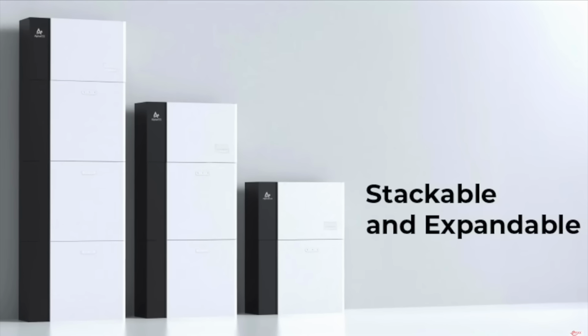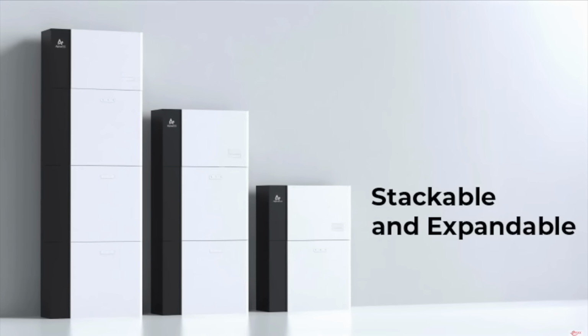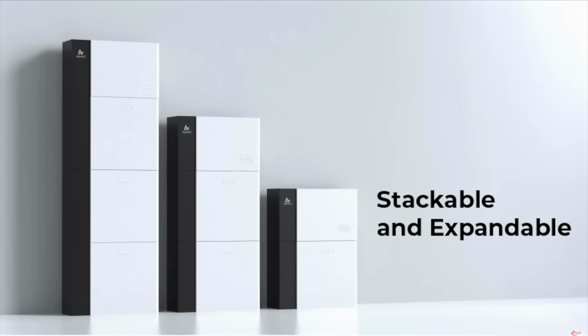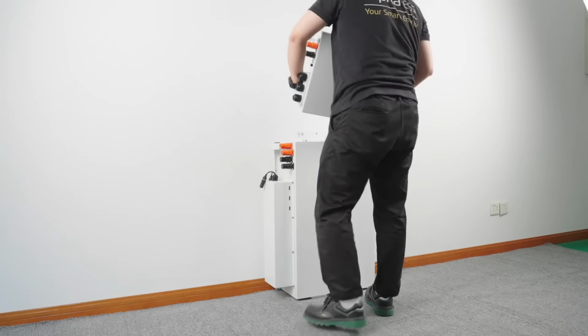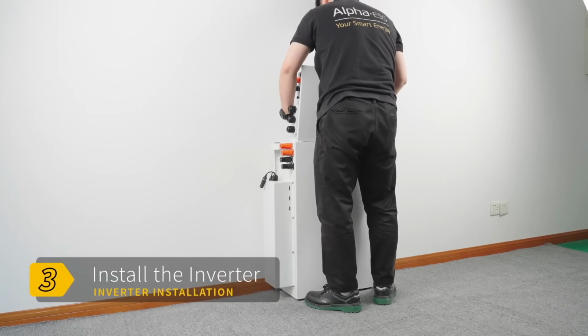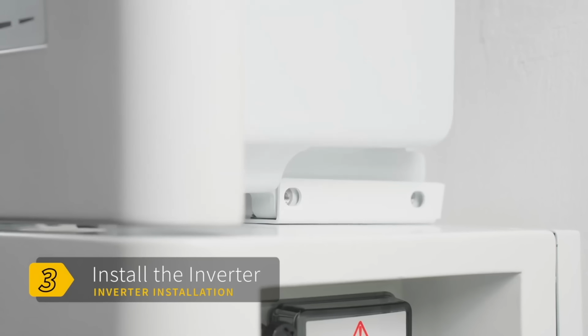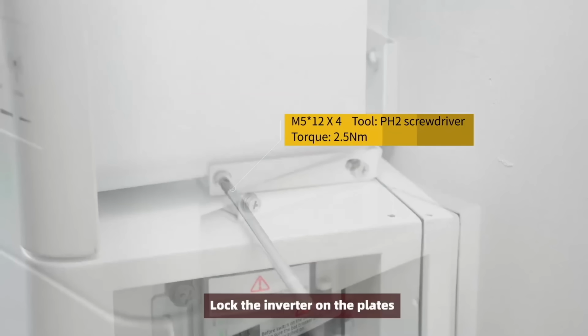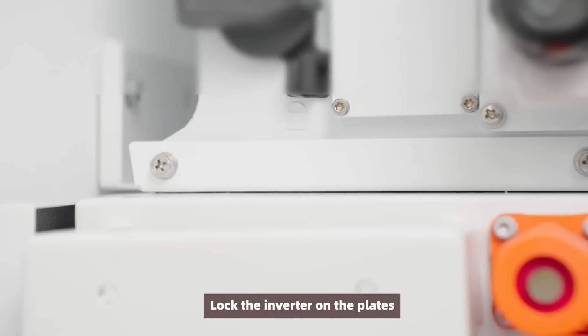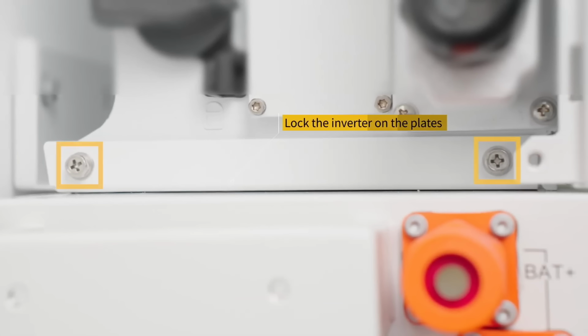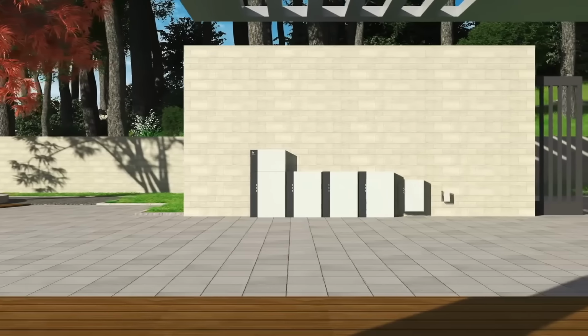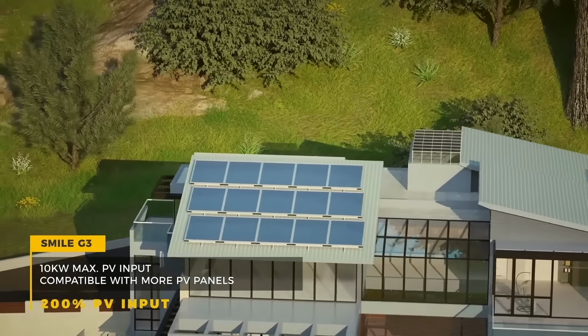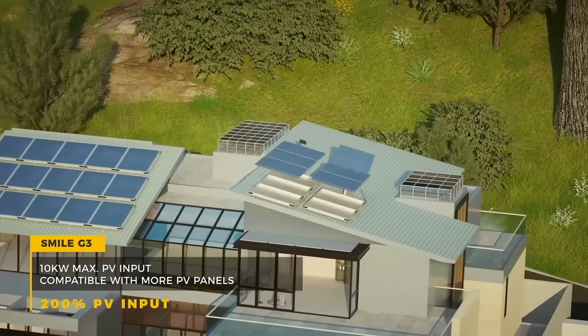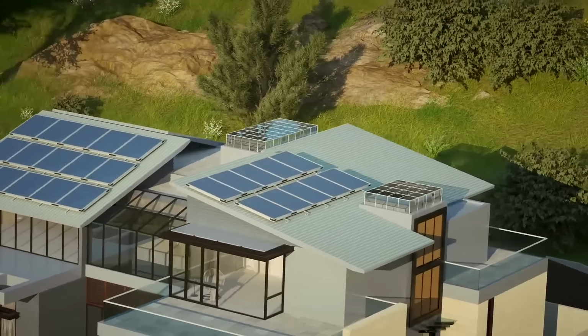This residential product comes in a range of ratings. There are single-phase options ranging from 3.6, 5 and 8 kilowatts, and three-phase inverters come in 10 and 20 kilowatts. All systems are on the ENA register and are fully compliant with G98, G99 and G100. The modular design means you can install it building-block style with plug-and-play connections to make it super easy. The inverters have the ability to PV oversize up to 200%, allowing you to send any excess to the batteries, while the inverter is sending the full kilowatt capability of the inverter to the property.